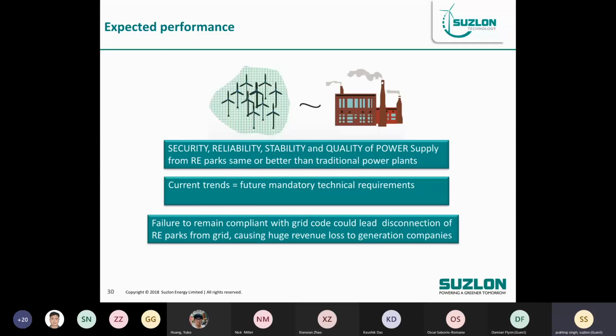For example, when talking about reactive power: you were asked to provide 100 MVAR of reactive power compensation for a park, and if 10 or 20 MVAR, that is 10-20%, is not available or faulty, the grid authority says it makes the system risky and a potential problem, so you have to reduce your generation to match your reactive power supply.